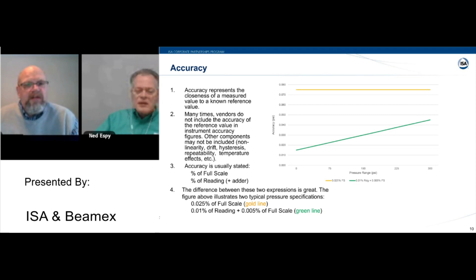So, Ned, I'd like to make a comment here. With regard to your second bullet, this is kind of what we used to call specmanship back when I was in the lab. When you're looking at spec sheets, you have to be very careful and read the fine print. It will somewhere tell you whether hysteresis and repeatability are included or not included in a particular spec. So when you see those asterisks or footnotes, go to the bottom of the page and check what the accuracy spec they're talking about really includes. I just wanted to point that out: we need to be very careful about reading our spec sheets.